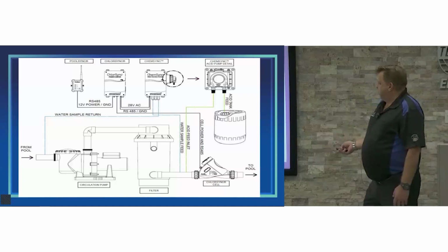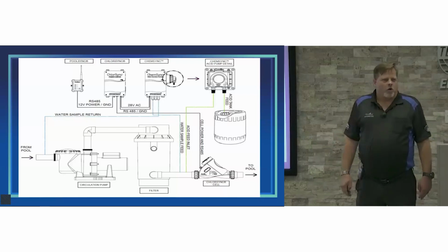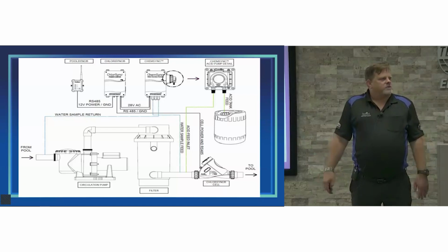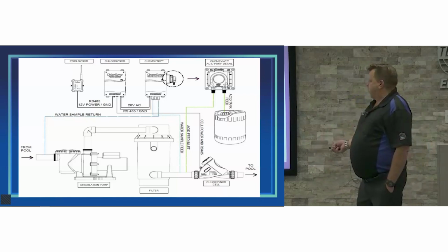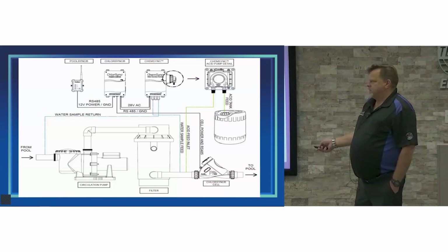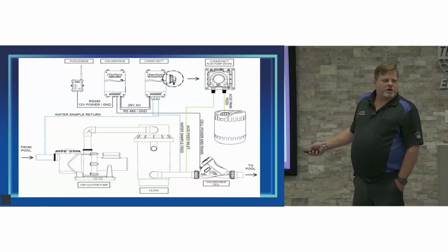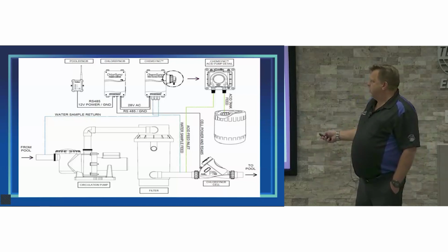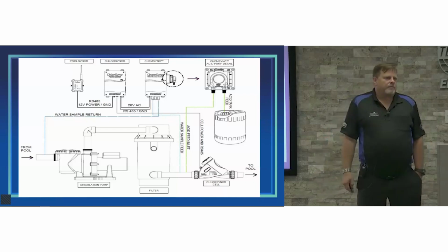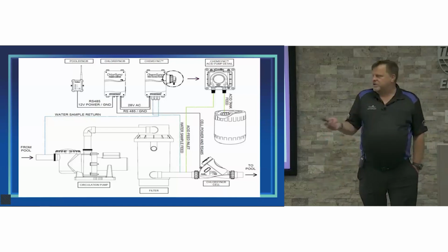Well, if this thing is sucking water out of the return line and there's no water in that return line, your pump's going to cavitate, and it's going to stay cavitated until it sucks all that air out of the return line. So if you make it a pressurized vessel, even if this loses prime, as long as the pump doesn't, and then fires up, it's going to push water into the return line, which is then going to fill the test chamber. So anybody have any questions on that?